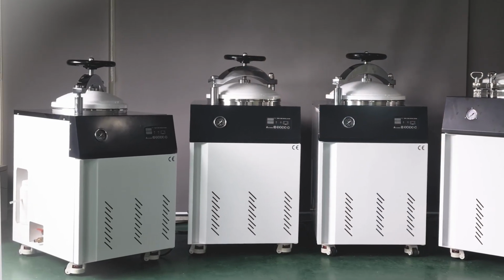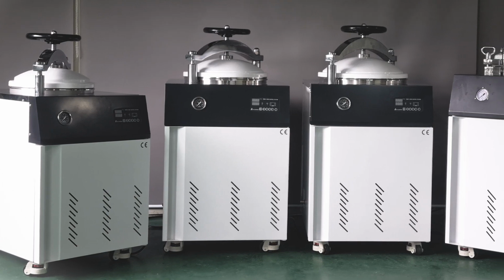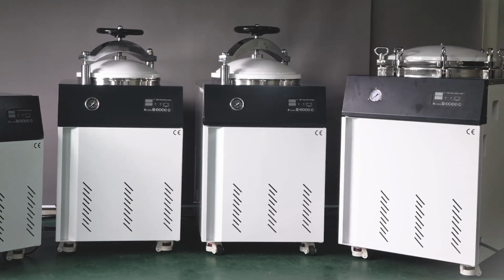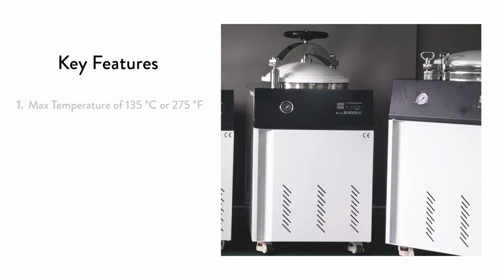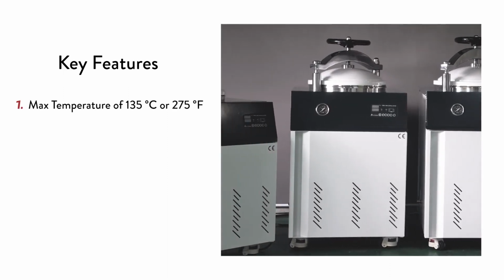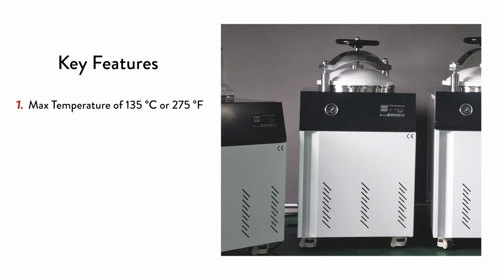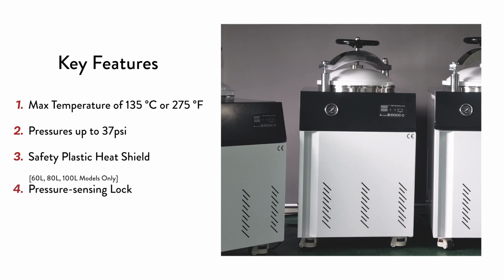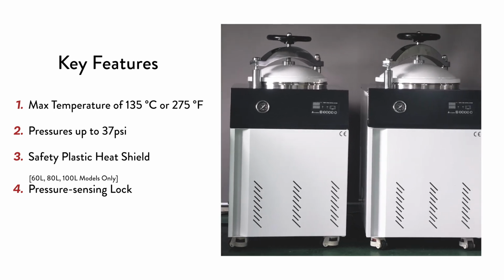Here are our medium and large-scale autoclaves of 60, 80, 100, and 150 liters. Each has a max operating temperature of 135 degrees Celsius, or 275 degrees Fahrenheit, at pressures up to 37 psi. When it comes to safety features, all models include a plastic heat shield on the door to prevent burns from the hot metal surface. The 60, 80, and 100 liter variations also have a pressure sensing lock, which automatically keeps the door closed as long as the chamber is pressurized.